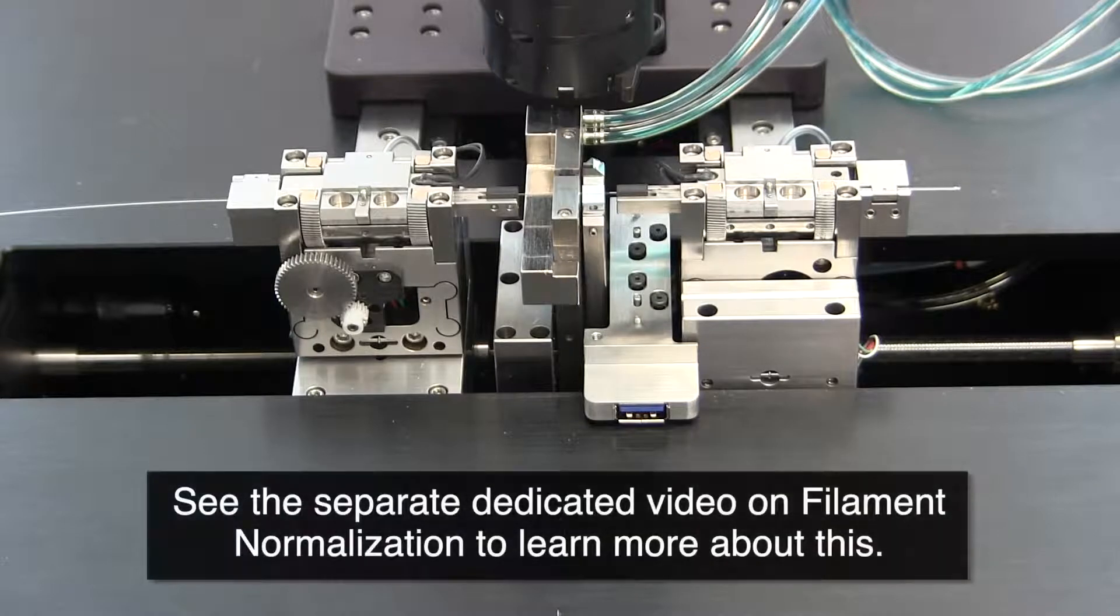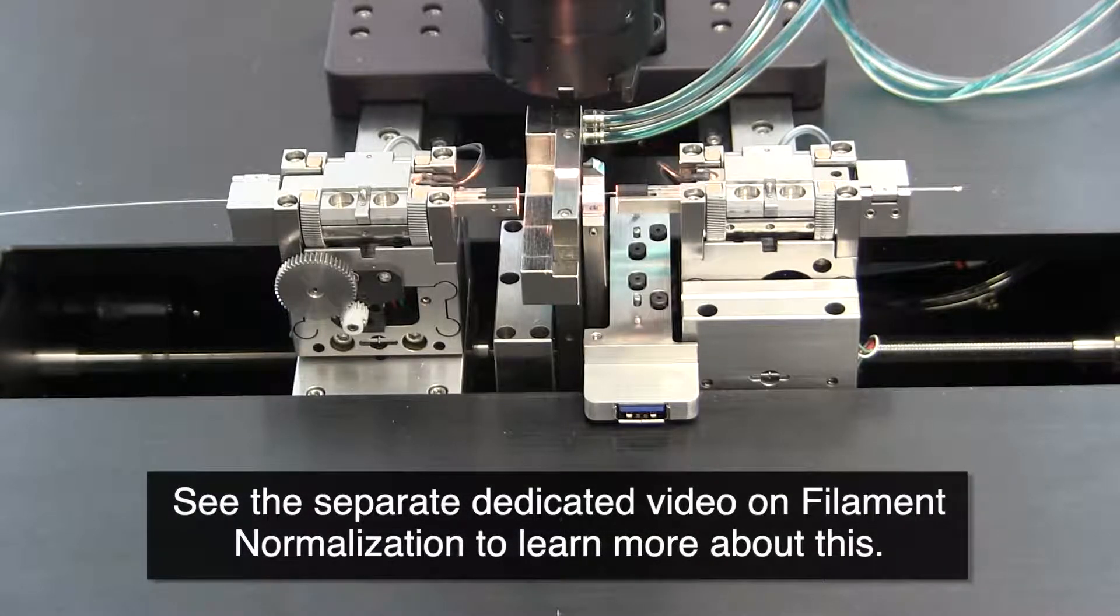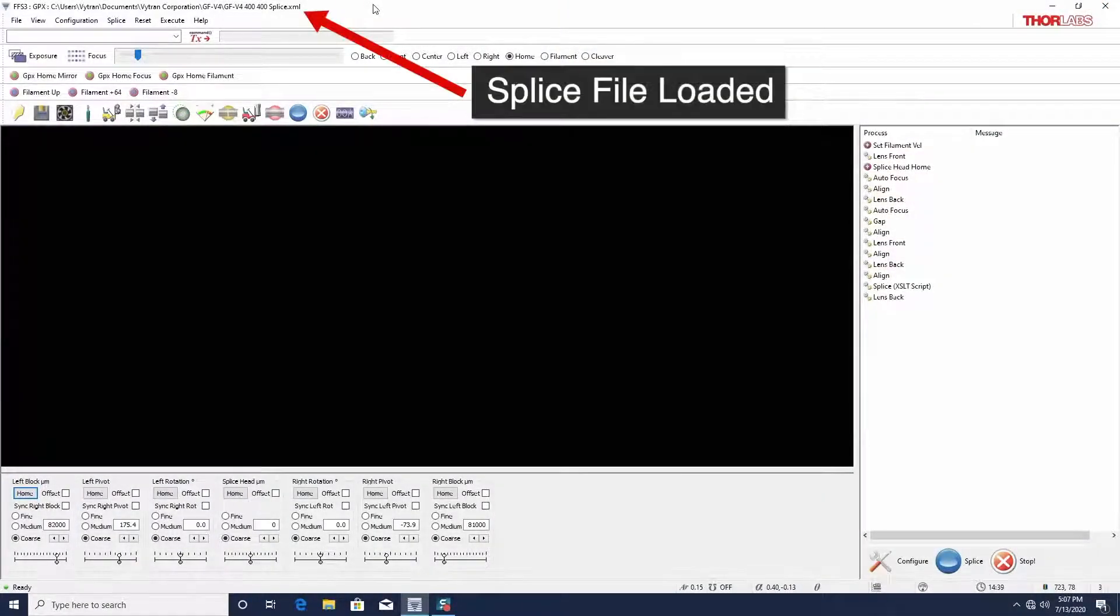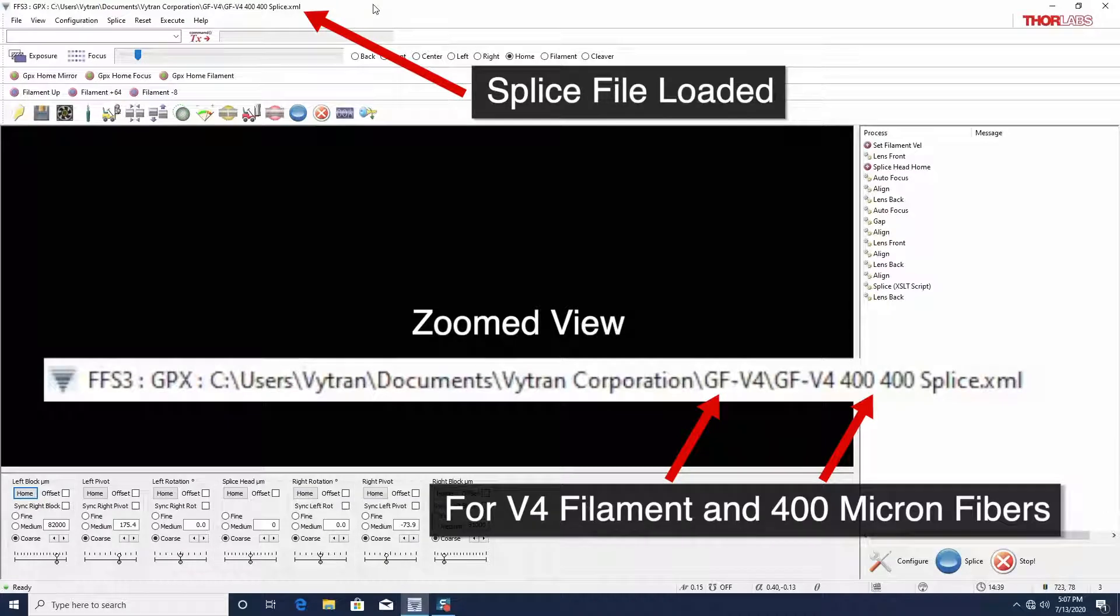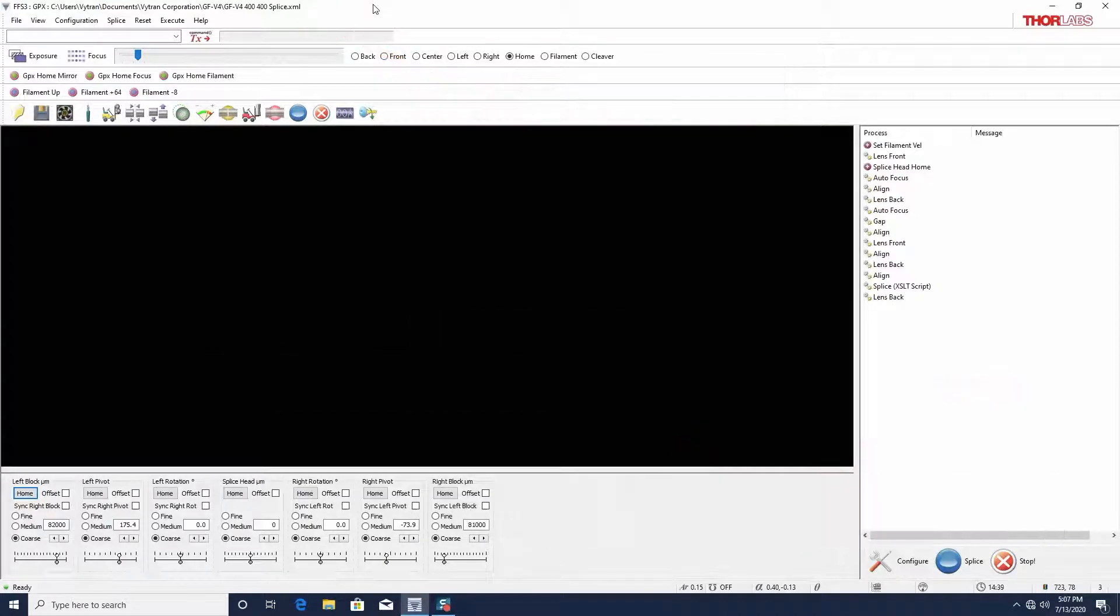For repeatable results, it is important that the filament be normalized first. Splice files for typical filament types and fiber diameters are pre-installed on the computer that ships with your unit. The parameters for a specific splice file can be viewed by going to the splice menu and selecting splice properties.